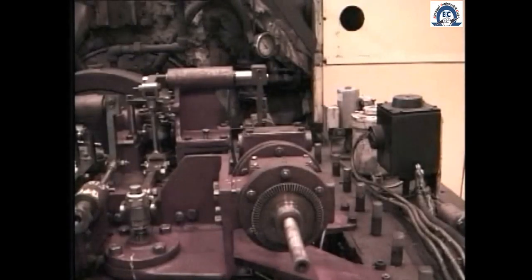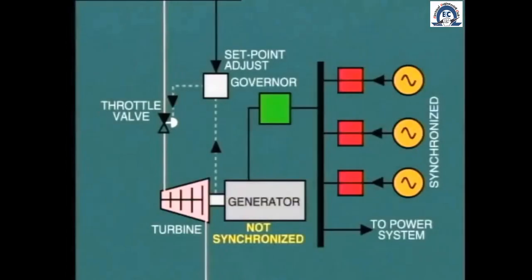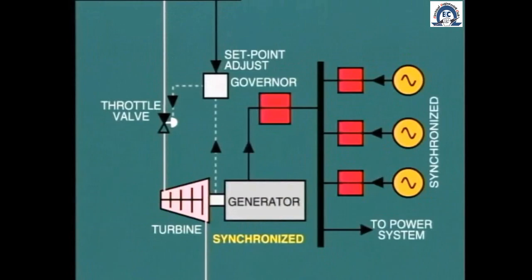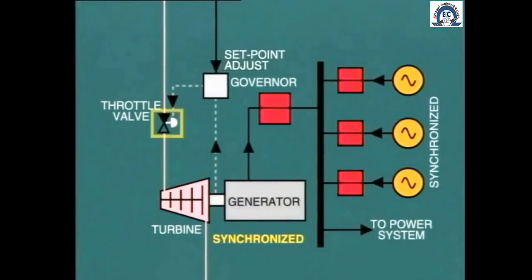Or, as is more usual, from a remote position by operation of a small motor drive known as the speeder gear. This name derives from the fact that when the turbine generator is not synchronized to the power system, any adjustment of the governor's set point will indeed alter the speed of the turbine. However, when the turbine is on load and the generator is synchronized to other machines, any adjustment of the speeder gear produces an imperceptible change in generator speed. Instead, this action causes a change in steam flow through the turbine with the consequence of a change in generator output.